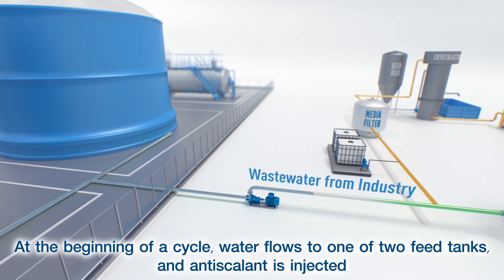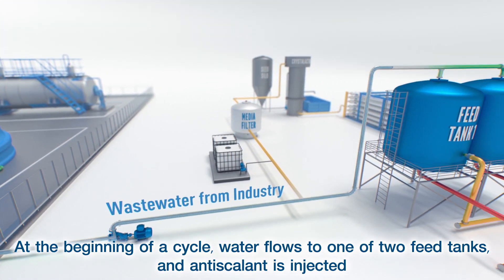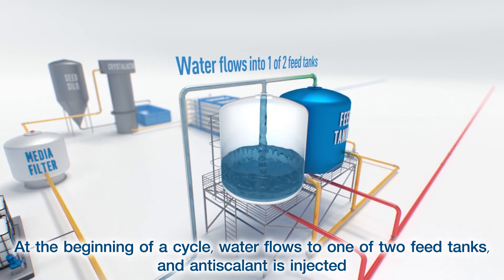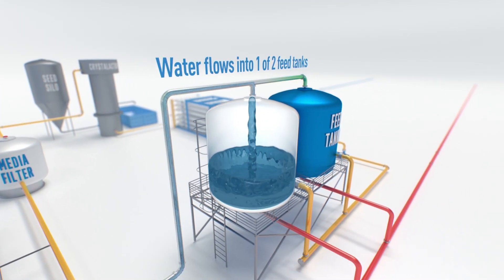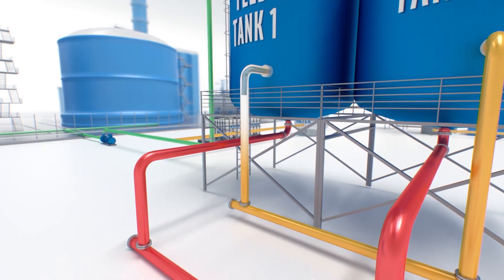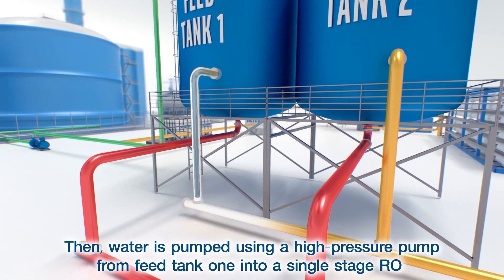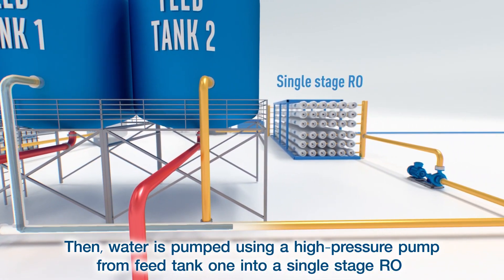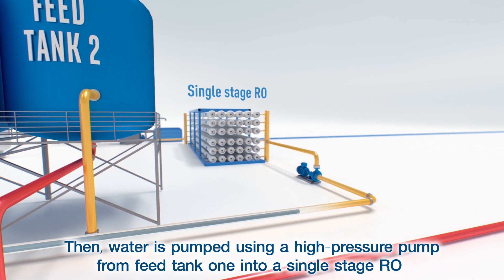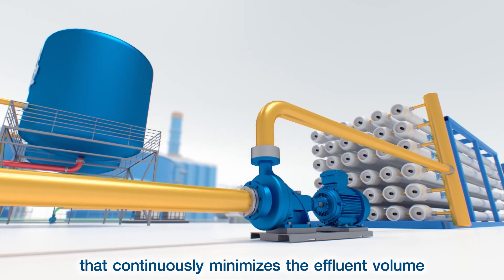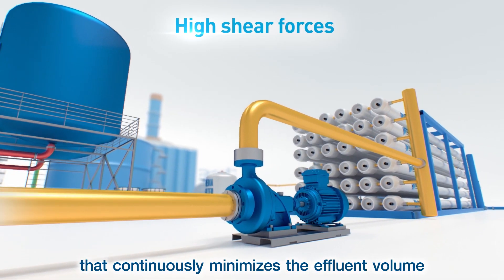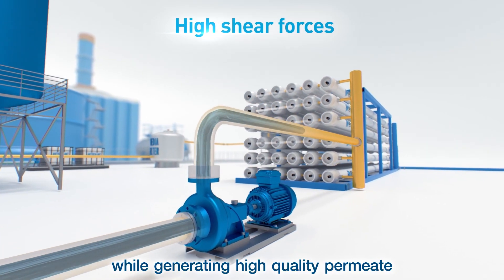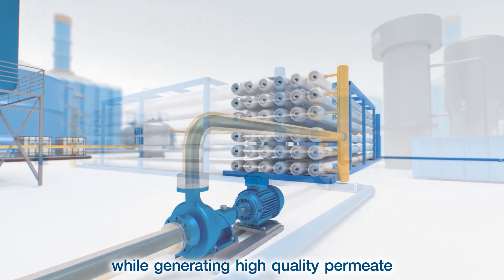At the beginning of a cycle, water flows to one of two feed tanks and anti-scalant is injected. Then water is pumped using a high-pressure pump from Feed Tank 1 into a single-stage RO that continuously minimizes the effluent volume while generating high-quality permeate.